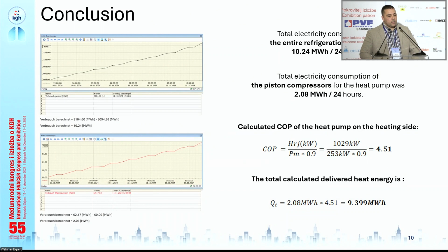The theoretical calculated COP for this system is semi-theoretical because we were already testing this system before, but we were taking that information from the data sheet, and the COP for the heating side should be 4.5. And when we take the information from the measuring unit, and we have 2.08 megawatt hours of electricity consumption from the heat pump compressors, we can calculate that the theoretical heat energy delivered to the heating system should be around 9 megawatt hours. And this is all measured in the 24-hour period for the testing.